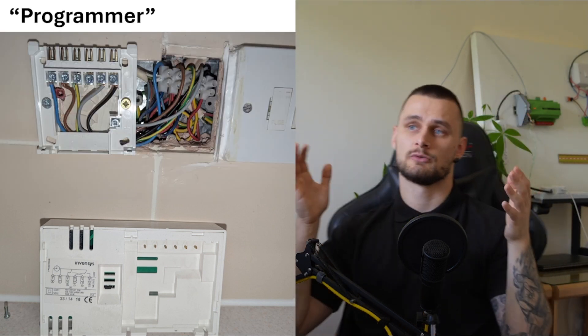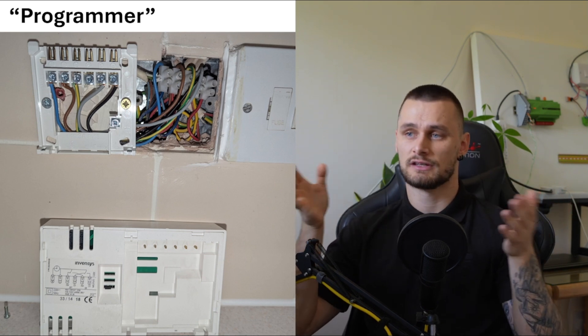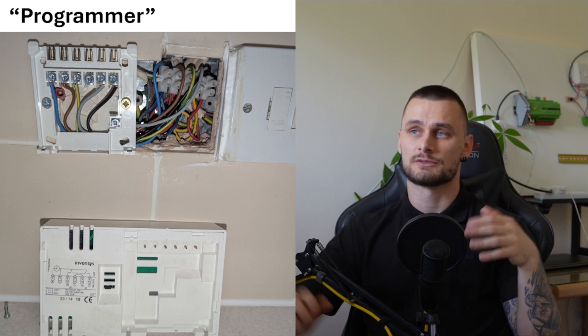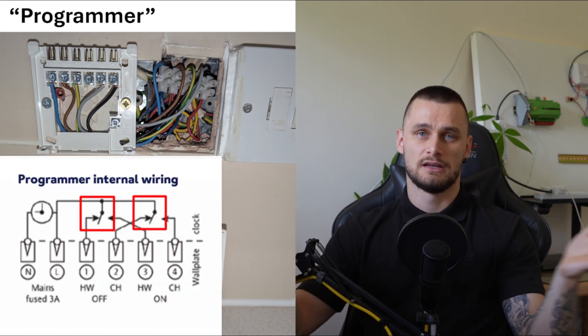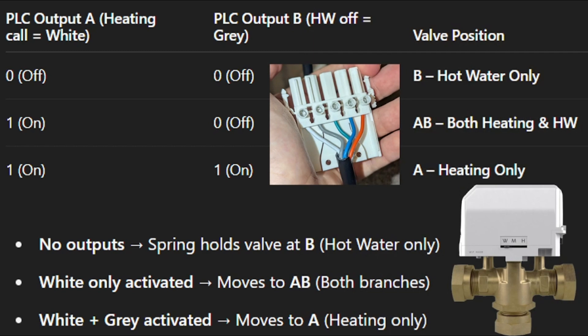If we want to go further and wire everything up, we need to think about the mid-position valve, which is the pivoting part of the system — it decides heating, hot water, or both. I've made a little diagram showing the logic. You have two relays, and depending on the combination of on and off, you decide whether you want hot water, heating, or both at the same time.